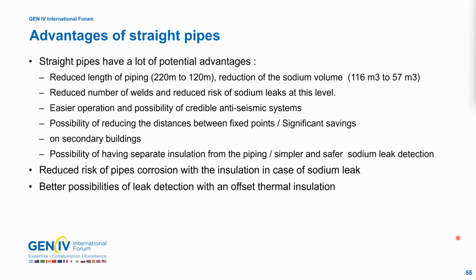We have easier operation of the plant and the possibility of a credible anti-seismic system, because you can have an anti-seismic system very firmly bolted. We can reduce the distance between the fixed points and get significant savings on secondary buildings. And we can separate the insulation from the piping. So it's simpler, it's safer, and it's a very big advantage for the operator of the plant for sodium leak detection. We have also reduced the risk of pipe corrosion because the insulation is no longer in contact with the pipes. And we have better possibilities of leak detection with an offset thermal insulation. Thanks. Next slide.